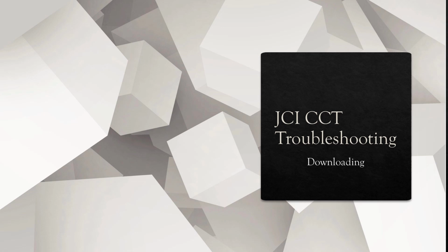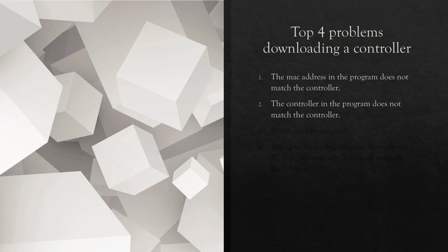All right, let's talk about downloading. Four problems downloading to a controller. MAC address is wrong. It does not match. That's probably the number one problem that I see everywhere.